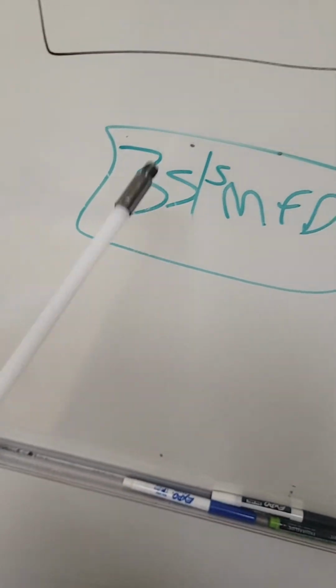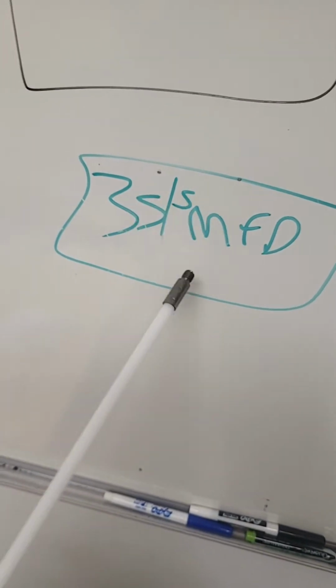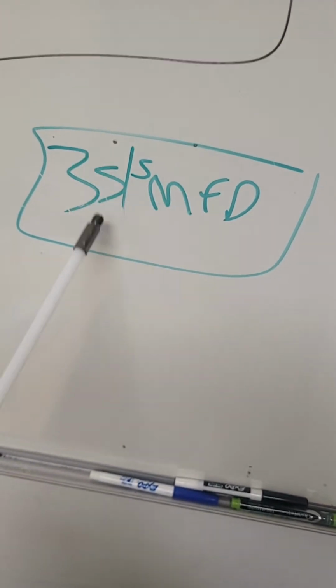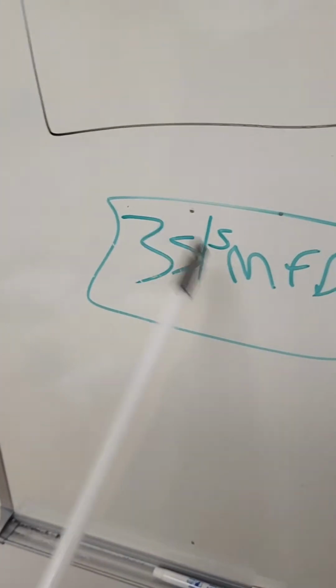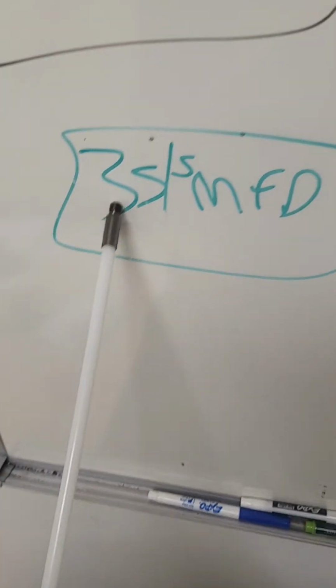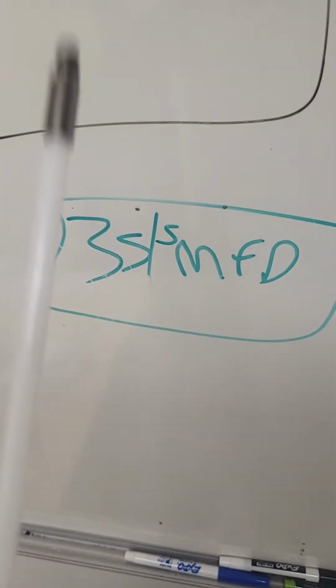Here's the thing, guys, I'll reiterate this: you should always abide by what you took out. If you took out a 35-5 and can verify that was the original size capacitor for the unit, this is for an outdoor AC system, a dual cap, not the run cap inside, you should always put in the same size, whatever you take out.